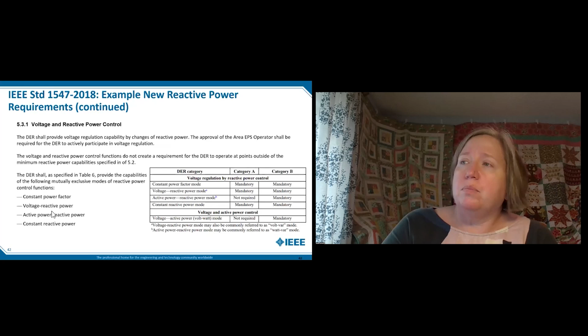So there are 4 voltage and reactive power control modes. As I stated, they do not operate outside the reactive power capabilities as specified in 5.2. And so these are mutually exclusive: the constant power factor, the voltage reactive power known as volt-var, the active power reactive power, which is watt-var, and the constant reactive power. The 5th mode is actually an active power mode, the volt-watt, which can run with any of the reactive power control functions.